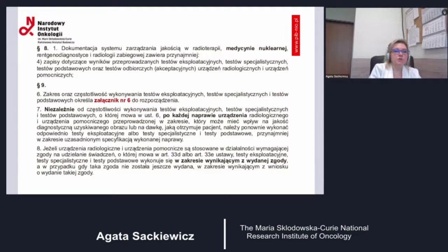Before I proceed with the presentation on some tests, I would like to refer to some pieces of legislation, some paragraphs that also relate to the performance of such tests. We need to remember paragraph 8, which concerns quality management system documentation in radiotherapy. So there must be some descriptions of the tests, the baseline, the performance, and specialized and acceptance tests for the specific pieces of equipment and ancillary equipment. And the next paragraph is paragraph 9, which lays down the extent and frequency of conducting the tests, regardless of the frequency of making the performance tests.